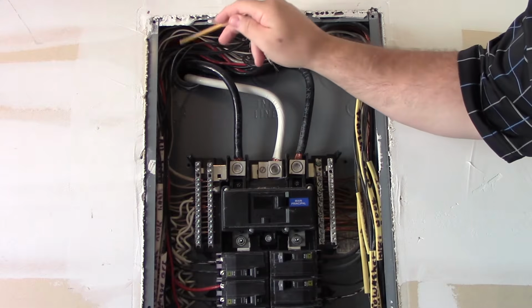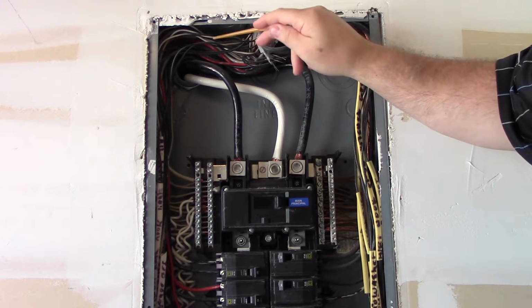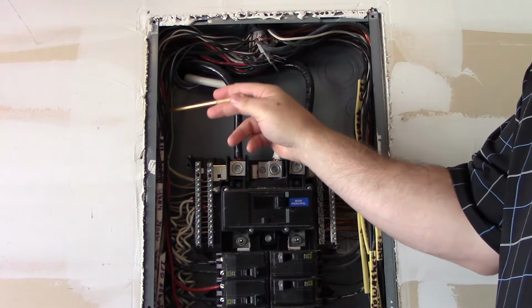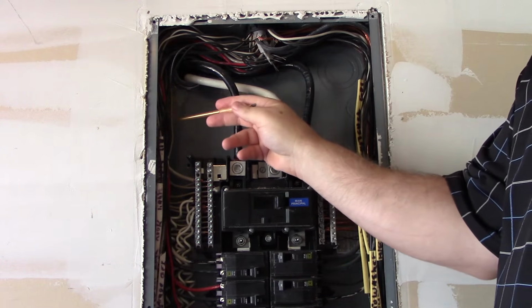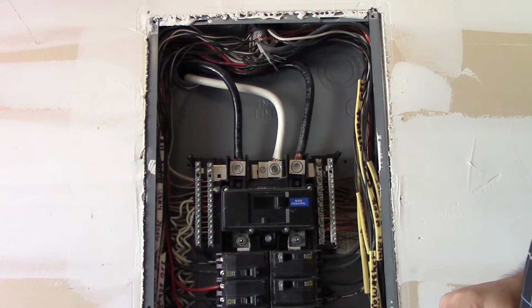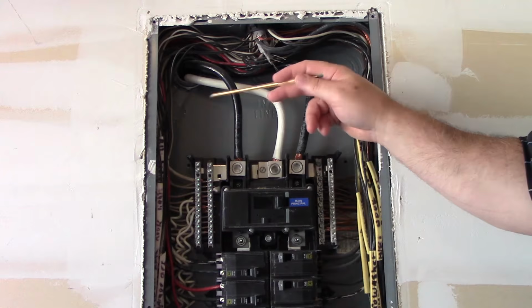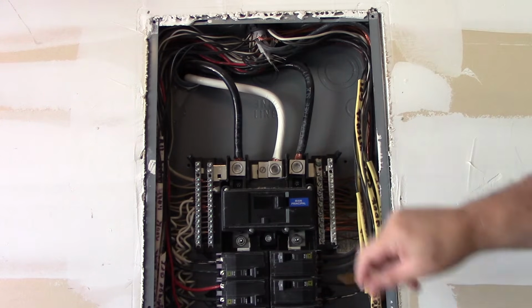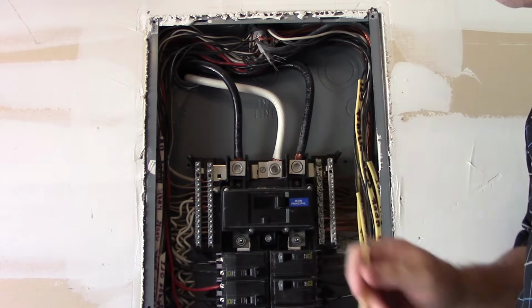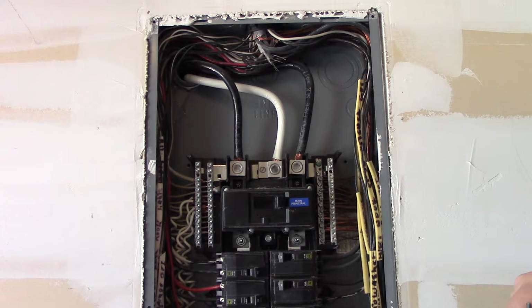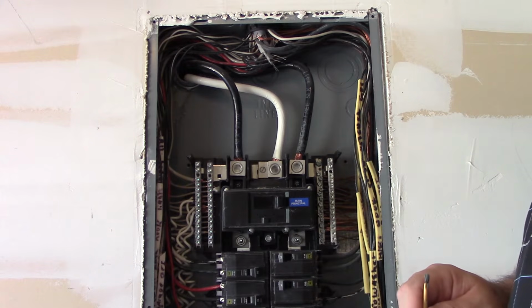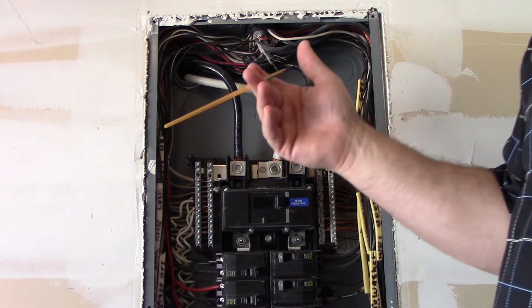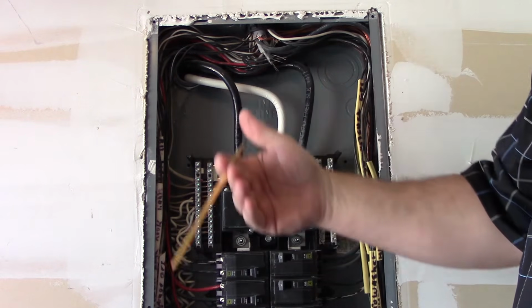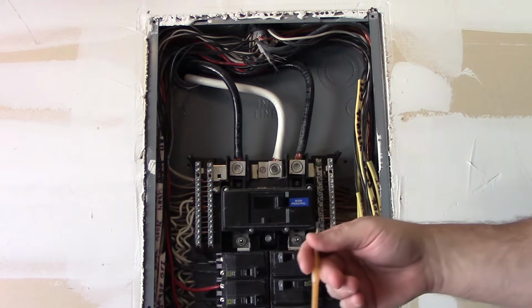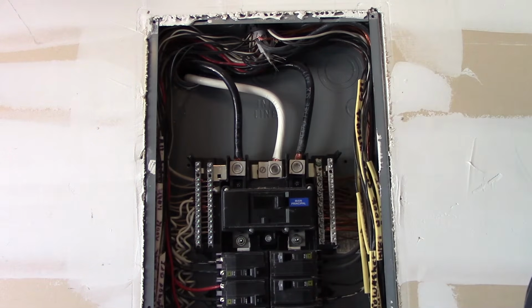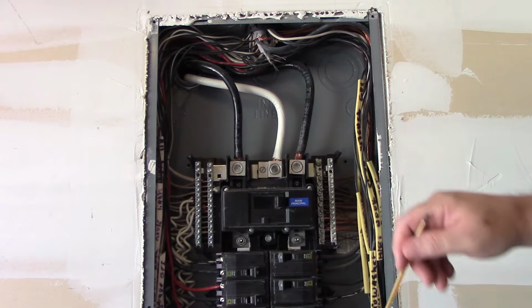Now, I'm going to look at all these individual conductors here, all these wires, and I'm going to look for anything that looks like evidence of damage. Anything that looks like it's scorching, anything where they damaged or cut into any of it when they stripped it out of the actual cable. I'm going to look at all those aspects, and I'm kind of going to give it a visual around it. I've looked at this one, and I don't see any damage anywhere. None of the colors look faded out, or none of the insulation looks damaged or anything like that. And when I say faded out, sometimes when you strip it and they accidentally do it with a knife, you'll see some areas that look faded out in color, and that's because they stripped off the outer color. So I'm looking for those type of things. I don't see anything with that. So everything looks good. No damage there.